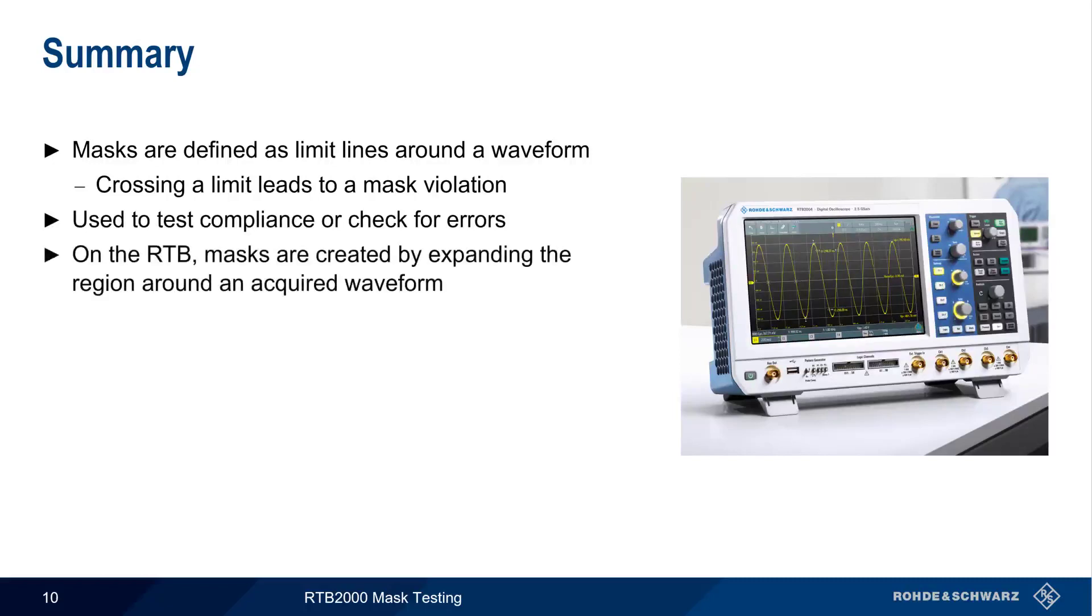On the RTB, masks are created by first acquiring a waveform, and then expanding or scaling the region around this acquired waveform. This can be done in several different ways. Once the mask is created, a mask test can be run, which yields both counts and percentages of compliant and non-compliant waveforms.